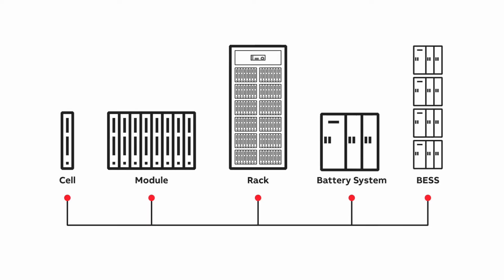So for example, if we take a product on lithium-ion, we start from having lithium-ion cells, assembling them into a battery module in series and parallel connection to get a first level of battery management system, which is managing the parameters of the battery cells, like the voltage and temperature. Then we connect these battery modules in series to build up a battery rack to achieve the voltage needed by the power conversion unit that needs to be connected. Again, in this case, we have another layer of battery management system. On top of that, we need to connect in parallel different racks to achieve the energy and the power needed by the application. And again, in this case, we have a third layer of battery management system, which is managing all the racks down to the single cell.